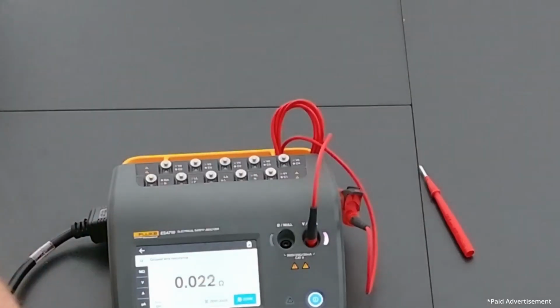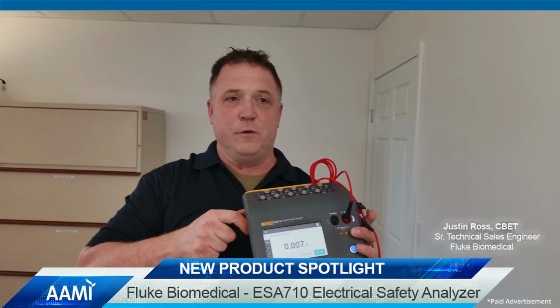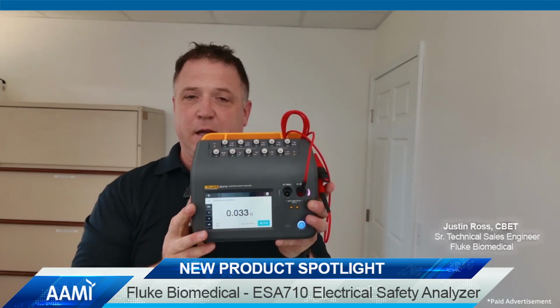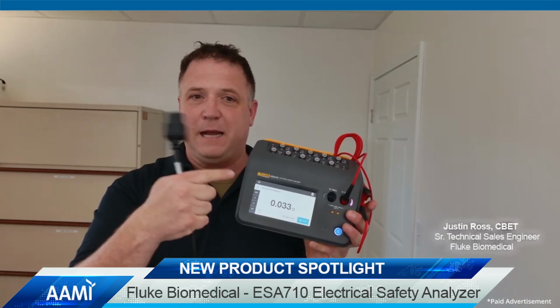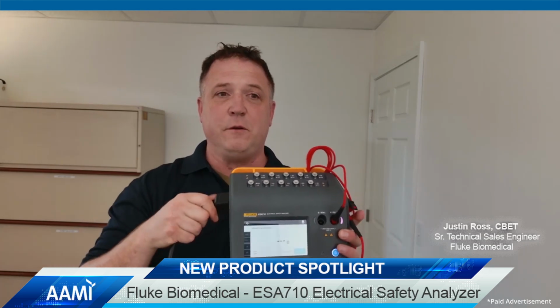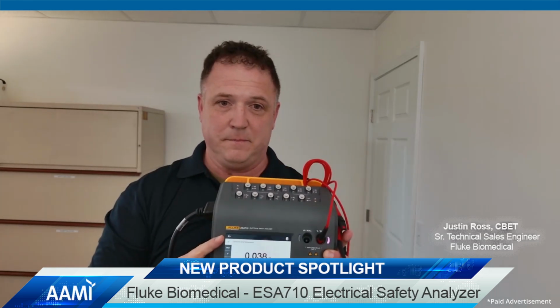Now, if that wasn't cool enough, let's do this. If I'm taking my safety analyzer and I'm just walking down the hallway doing my job and I need to move, you'll notice that I just unplugged the cord and there's no more power to the device, and I'm moving down the hallway. Battery backup. So I can move down my hallway, move to my next device that I need to test, simply plug in to do my electrical safety, and when it's doing that, it's going to charge the internal battery.